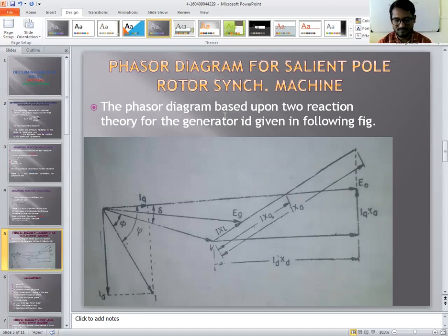These are the precautions. While carrying out the slip test, the first precaution is that the slip should be kept extremely low, as a high slip of more than about 5% causes appreciable error in the reading of current induced in the damper winding of the alternator.